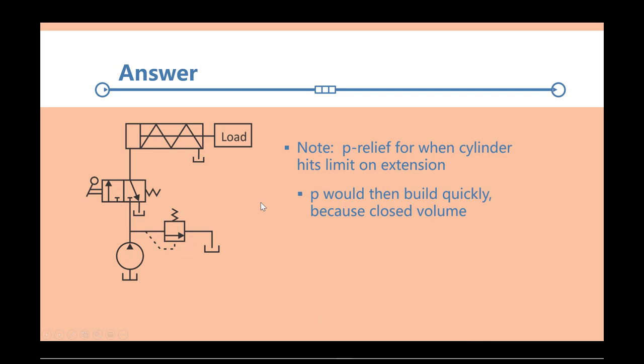Let's go on and see what we say here. So if you had this envelope active, and the cylinder extended, it would at some point reach the end of its stroke. And then you would have a trapped volume here also, or in general, you would have the pump pumping into a volume that would be closed, and the piston can't move anymore. So the pressure would build up, and the pressure relief valve would actuate, and the cylinder could just sit there, and the pump could then pump fluid through the pressure relief valve back into the tank.